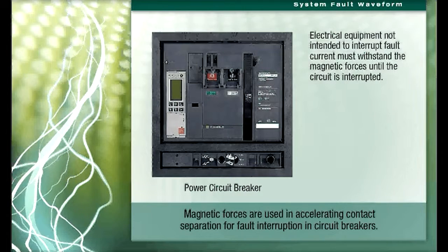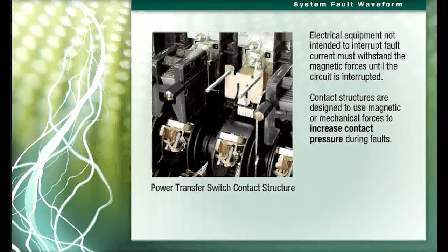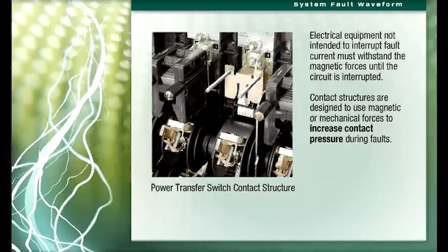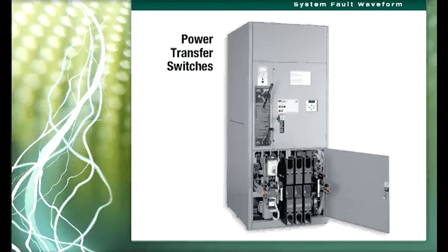Electrical equipment not intended to interrupt fault current must withstand the magnetic forces until the circuit is interrupted. Therefore, their contact structures are usually designed to use magnetic or mechanical forces to increase contact pressure during faults, allowing the protective device, such as a circuit breaker, to sacrifice itself in clearing the fault. Typically, this equipment would include power transfer switches, which have withstand current ratings qualified to UL 1008 transfer switch equipment standards.